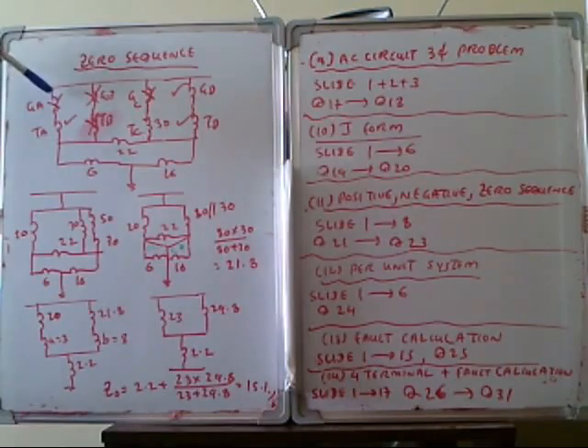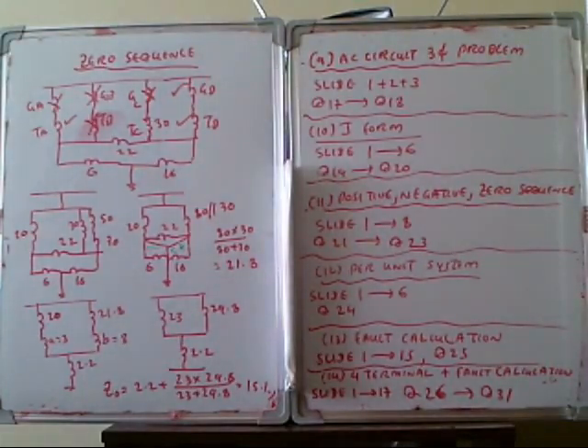So zero-sequence diagram, all the equipment connected to ground are to be included and any equipment that does not have the ground connection are to be removed. So in this way we get the zero-sequence diagram.